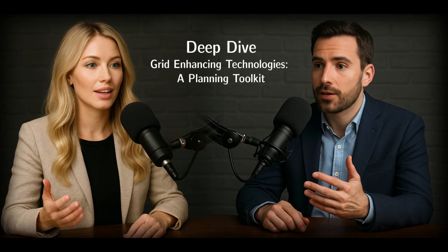There are several types. A common one is ACSS, aluminum conductor steel supported. That typically gives you about a 25% capacity increase. Okay. Then there's ACCC, aluminum conductor composite core. This one uses a lightweight composite core and can offer a much bigger jump, 50 to even 100% capacity increase. Double the capacity on the same towers. Potentially, yes. There are also gap-type conductors designed to manage thermal expansion differently, and specialty alloys for really extreme temperature or environmental conditions.